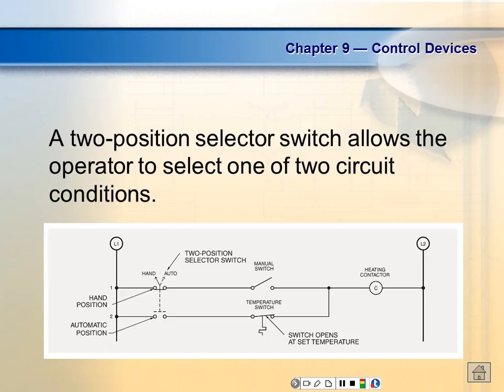Are y'all okay here? Couldn't y'all see how it works? So here's the way they represent which contact closes. Up here on auto, they have a dashed line. This is the contact that would close when you put it on auto. This one has a solid line, so this contact would open when you put it on auto. It would close when you put it on hand.